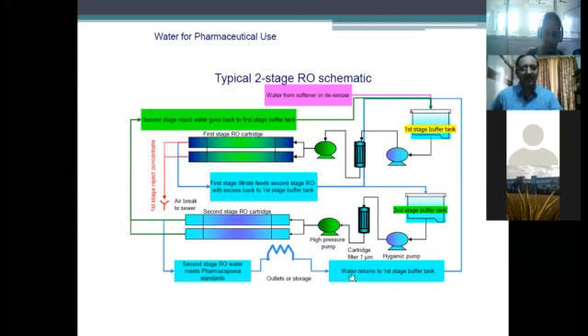Here you can see, this is a heater, so it is kept heated and kept under circulation. Water returns to the first stage buffer tank, so that recirculation is done to maintain the water under pathogen-free conditions.